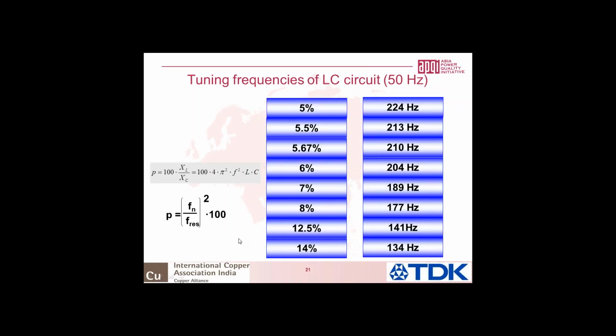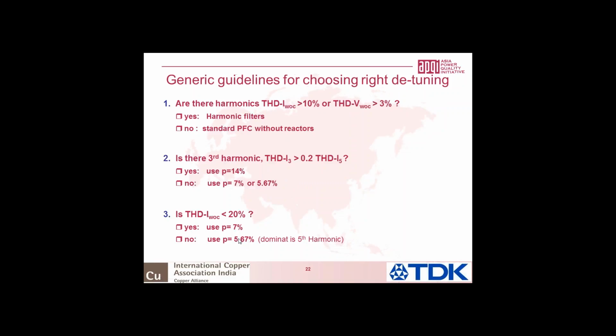When the THD-I without capacitor, WOC, which stands for without capacitor bank, is greater than 10%, then I say use harmonic filters. Otherwise, use standard PFC without reactors. If you have a third harmonic which is more than 20% of the fifth harmonic, that means you've got a third harmonic excess in your system, which means you need detuning, so use a 14% reactor. Otherwise use a 7% or a 5.67% reactor. If the fifth harmonic current is less than 20%, then use a 7%, otherwise use a 5.67%, because 5.67% does eliminate a part of the fifth harmonic.